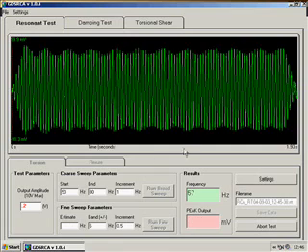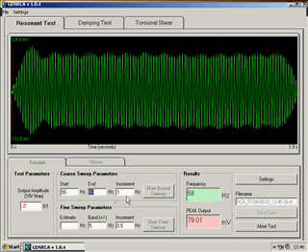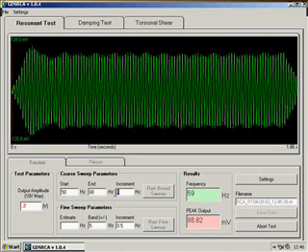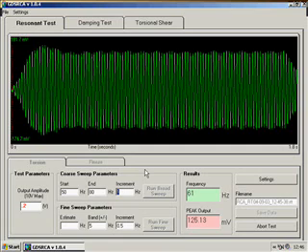We can see the test here runs through our selected frequencies from 50 to 80 hertz in steps of 1 hertz as we have defined. The test takes about another two minutes to complete, so we will return to the test when it is near completion.